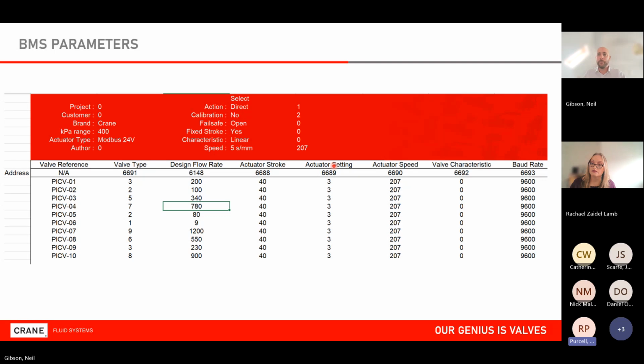Okay, so how much does that affect the rangeability, say, of the valve and the fine adjustment of the valve itself? Yeah. So it doesn't change it from the way that we traditionally set them up now, in the sense that we have a reducing stroke PICV. So even if we needed to do it manually, you adjust it and the stem stroke reduces. The rangeability is driven primarily from the actuator itself. So we're still driving it to 100%, albeit, yes, on a shorter stroke length. In theory, it shouldn't cause any issues. We still have 100 to 1. We can drive it in 1% increments, etc. But on a reduced stroke length, so you wouldn't expect the same level of granularity had it been at maximum setting. Yeah. Okay.